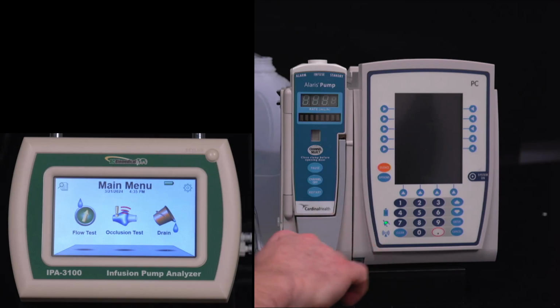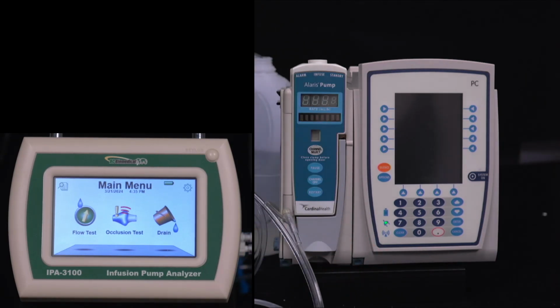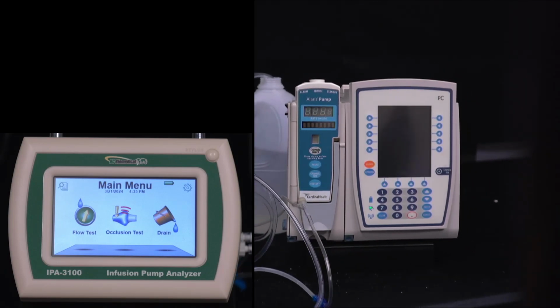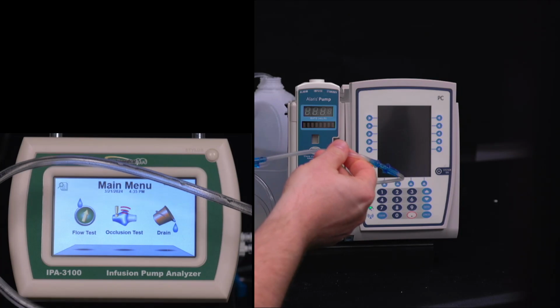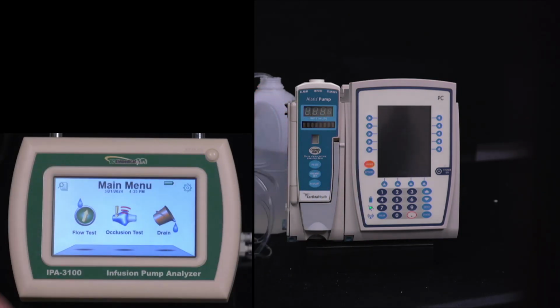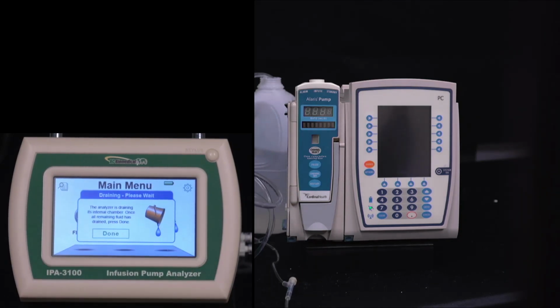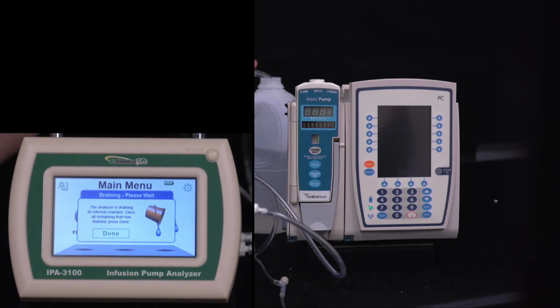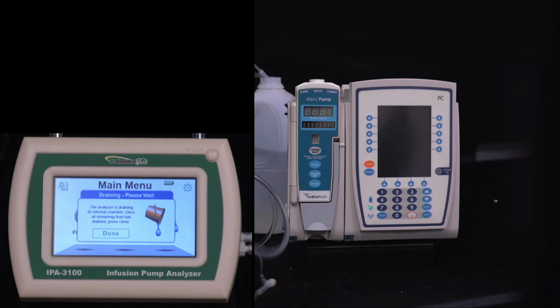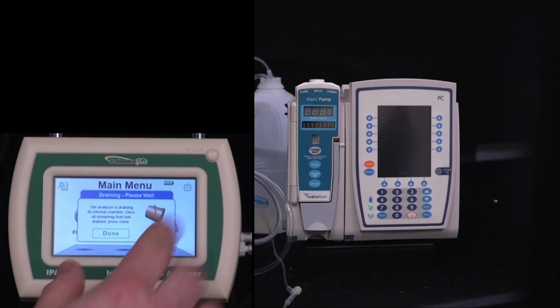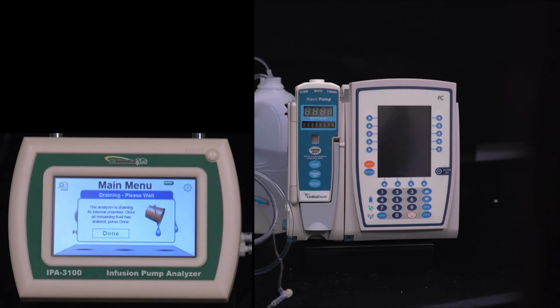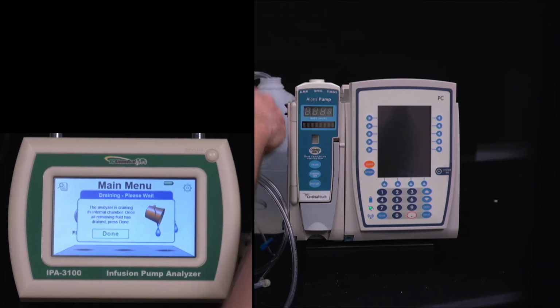Now I'm starting with my administration set. Let's see if I've zoomed out far enough so that you guys can get a better view of everything here. So this is my administration set and it's completely empty. So what I'm going to do is actually cheat here, and I'm going to use the drain function of the IPA 3100, make sure that my tubing is in the tank there. Now normally I would have that water back here, I would have that up on an IV pole, or they specify it has to be 20 inches above the pump for running testing. For this demonstration I've just got a little 1 gallon jug just so that it fits on the table here. Now we can see the water starting to come through the tubing.